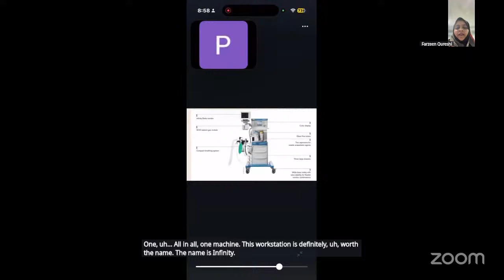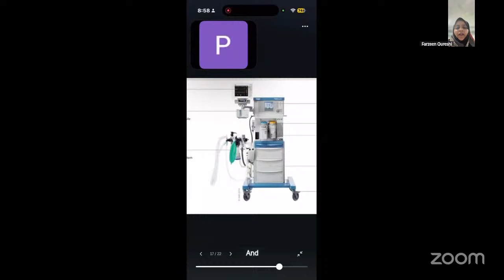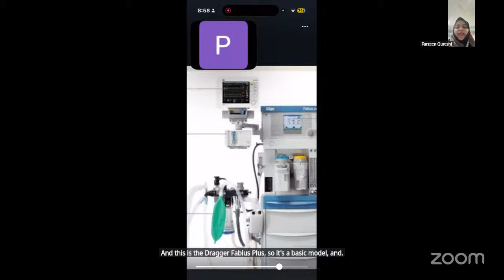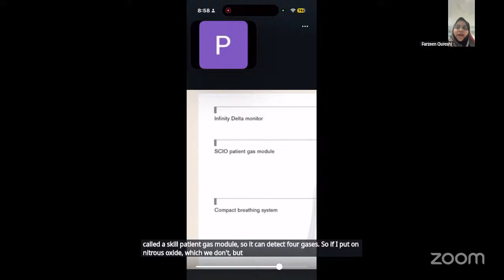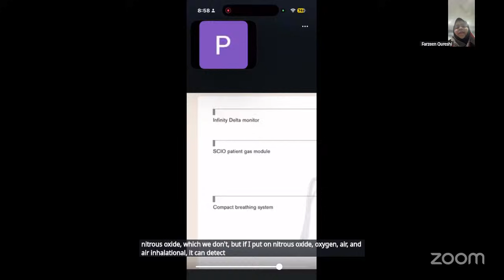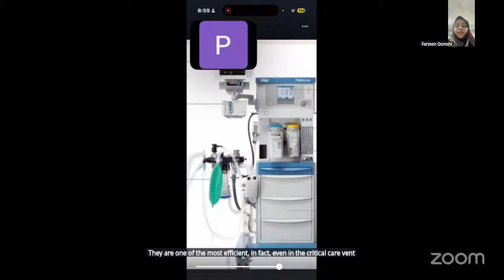And this is the workstation which we are using in our hospital. And this is the Draeger Fabius Plus. So it's a basic model. And we have the inbuilt gas monitoring systems right inside our monitor, and that also is a four gas module. I think it's called a Scio patient gas module. So it can detect 4 gases. So if I put on nitrous oxide, which we don't, but if I put on nitrous oxide, oxygen, air, and our inhalational, it can detect all 4 at the same time. And the Draeger advantage is that the ventilator pistons are very efficient. They are one of the most efficient. In fact, even in critical care, Draeger ventilators are really efficient in ventilating the patient. So that's another advantage of Draeger.